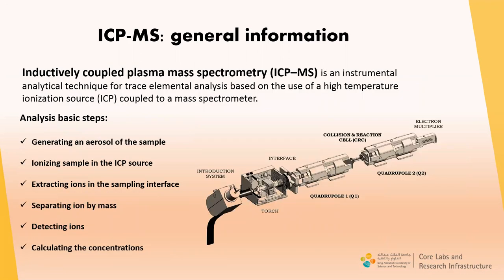Inductively coupled plasma mass spectrometry is an instrumental analytical technique for trace elemental analysis based on the use of a high-temperature ionization source coupled to a mass spectrometer. To carry out elemental analysis using ICP-MS, it is necessary to perform the following steps: generate an aerosol of the sample using a nebulizer, ionize the sample in the inductively coupled plasma, extract ions at the interface, separate ions by mass filter, detect ions by electron multiplier, and finally calculate the concentrations using calibration curves.